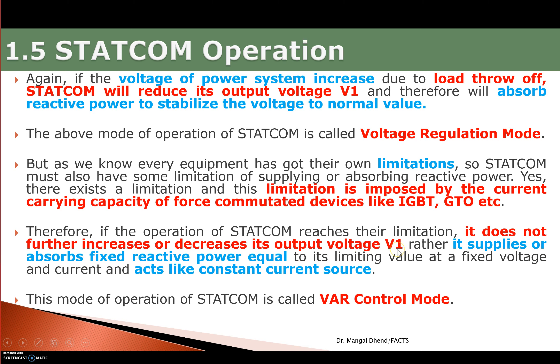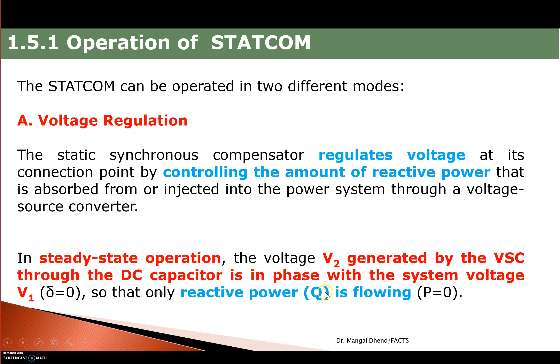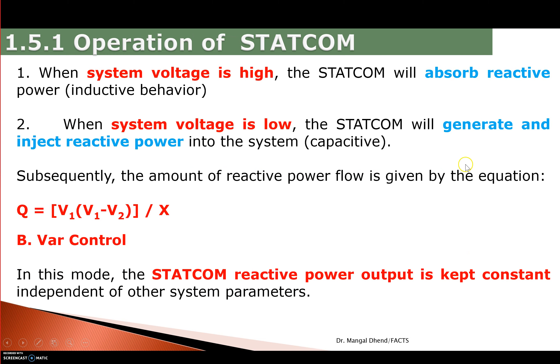When limitations on changing V1 are reached — that is, when voltage can neither be increased nor decreased further — STATCOM enters VAR control mode. In VAR control mode, the current through STATCOM remains constant. In voltage regulation mode, V1 and V2 magnitudes differ while phase angle difference is zero, so real power flow P is zero and only reactive power Q flows. The reactive power equation Q = V1 × ΔV / X governs this, and with delta equal to zero, the real power equation gives P = 0.